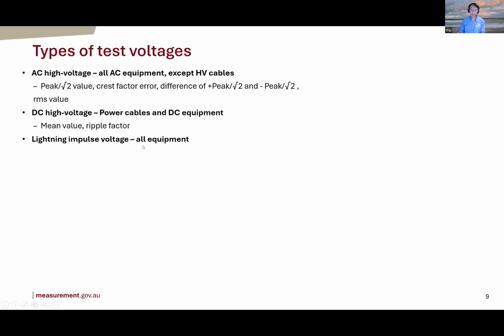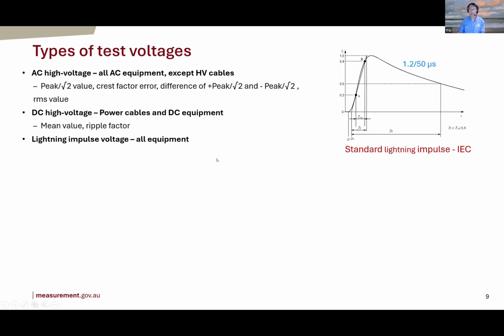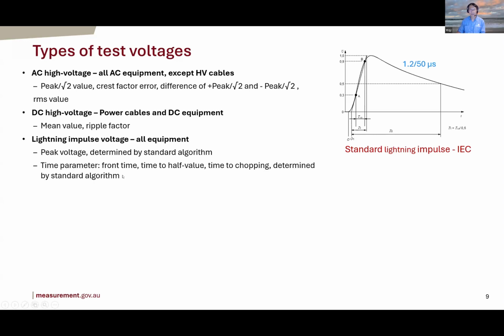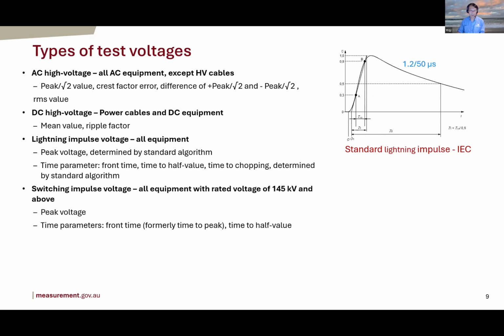A lightning impulse is simply a simulation of lightning strikes, but with standardized waveforms. Do you see that? Okay, it's a fast 1.2 microsecond rise and about a 50 microsecond time to half value. So it's quite a fast pulse, but it needs to be used for testing all equipment. The parameters to measure are the peak voltage and the time parameters. But these are determined by a standardized algorithm. You can't use your own. That's the current standard. We'll talk a bit more later. And then you have the operation of circuit breakers and disconnectors. This equipment generates switching impulses that will put extra stress on the equipment. So this is also a standardized type of impulse used in the laboratory for testing equipment.